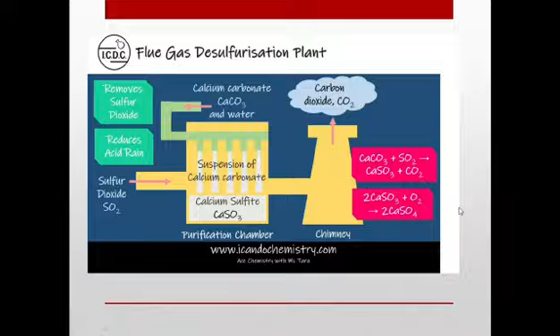This is a diagrammatic representation of the tower that is used to desulfurize the flue gas. This is the place where the flue gas is injected into this tower, and limestone slurry is injected from this side. From here, flue gas enters, and these are the spaces from which slurry is sprayed. And slurry means a paste of calcium carbonate or calcium hydroxide.